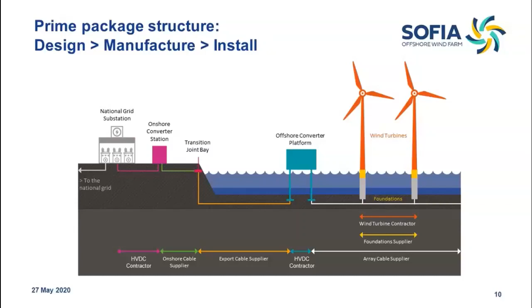Just a schematic of the farm, or the components. So we have wind turbines, and it's obviously not to scale. The wind turbines sit on foundations, and in our case there will be monopile foundations. They connect at 66 kilovolts through to a converter platform, which converts the AC electricity from the turbines into DC. We then transmit that through the export cable to a joint bay just onshore. There'll be an onshore cable, again in DC, to another converter station which converts it back to AC. Then there's a section of further AC cable through to the national grid substation, which connects into the main part of the national grid.